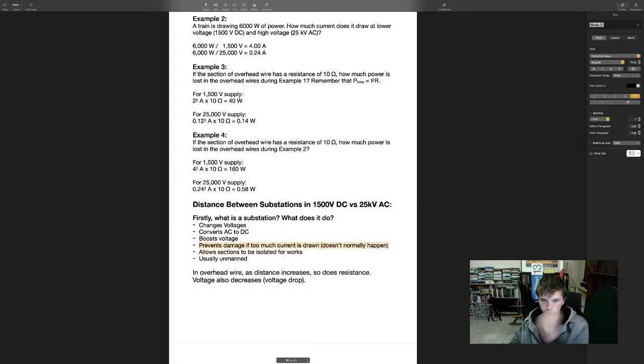That's another big thing that they do - it prevents major damage to equipment if too much current is drawn. In day-to-day operation, that doesn't happen, but when it does happen, it has the potential to go really badly. So substations will trip the breaker, which breaks the electric circuit, stops power from flowing, and stops things from getting too damaged.